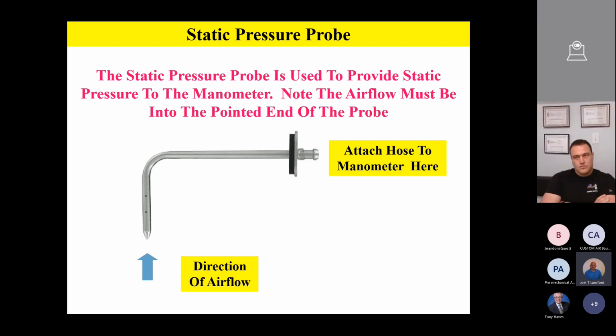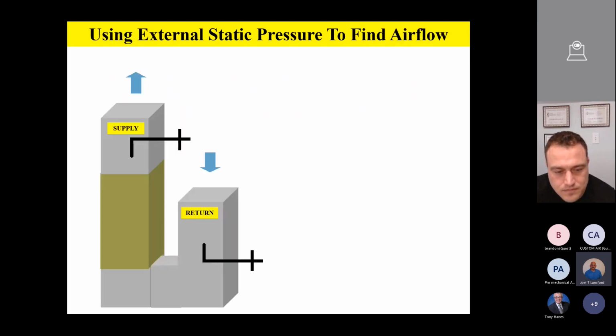If you have a filter like in a return grill and the ductwork comes down and hits the air handler, go ahead and just take it in the return ductwork, because what you'll actually be able to read is how much pressure that filter is adding to the return static pressure. And so you'll see in our graphic here in a minute how we have that hooked up. So basically, this would be a good example right here in this first graphic. You'll see our static pressure probes in the supply duct and in the return duct. Well, if my return air filter is downstream from the air handler, maybe in a closet or in a hallway somewhere, what we're reading right now is the total static pressure, including that filter.